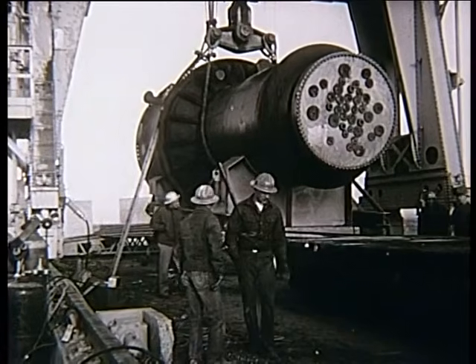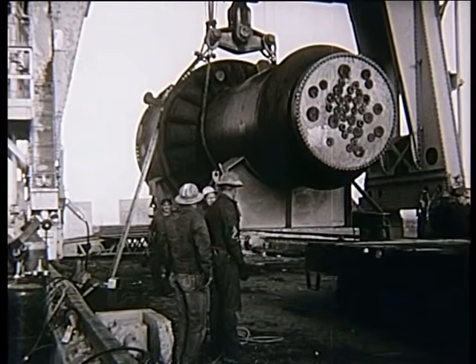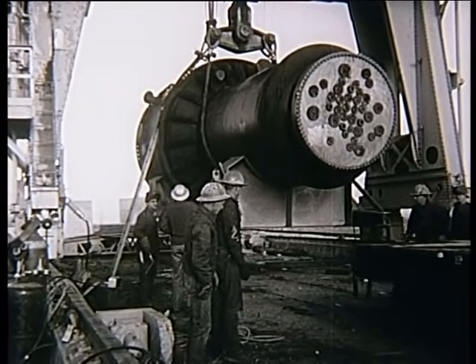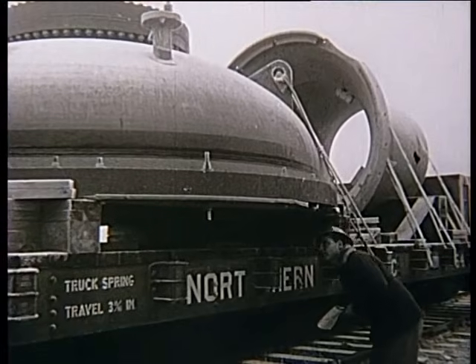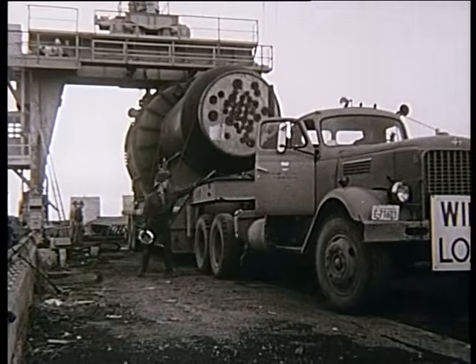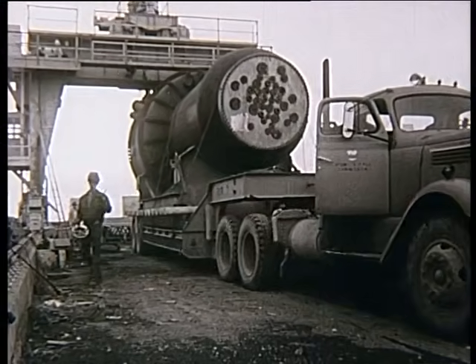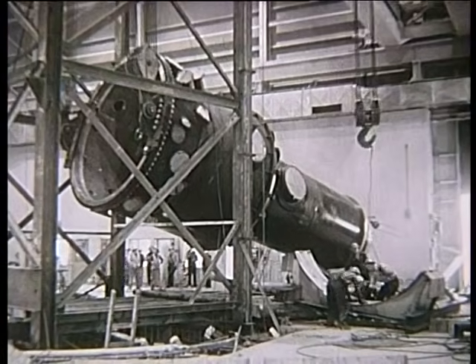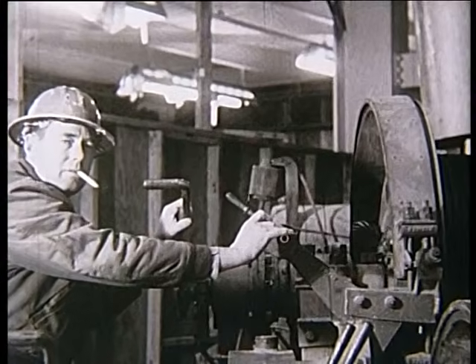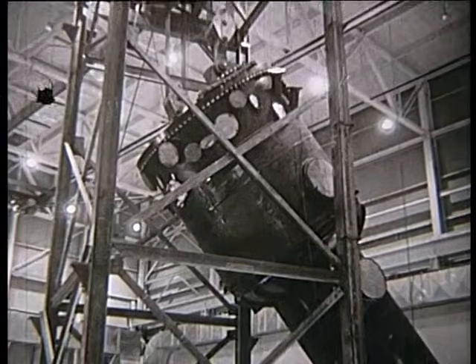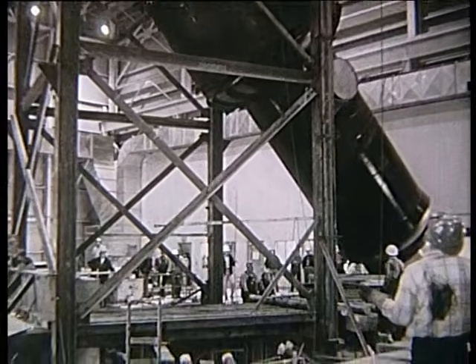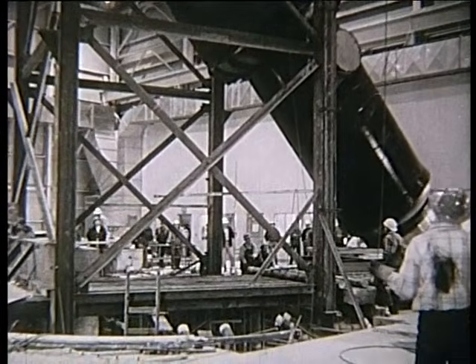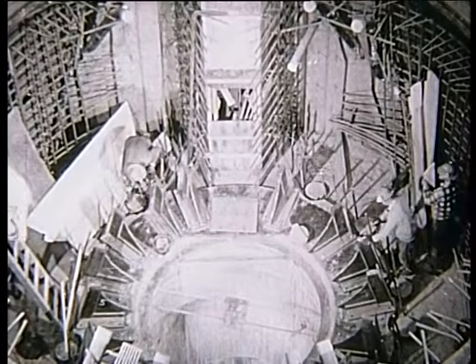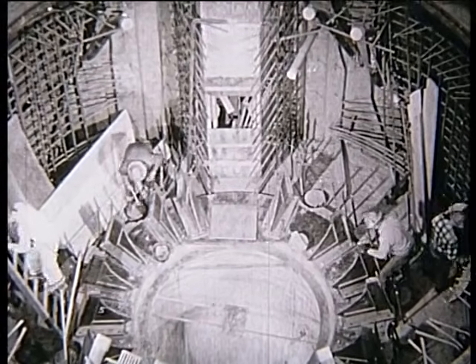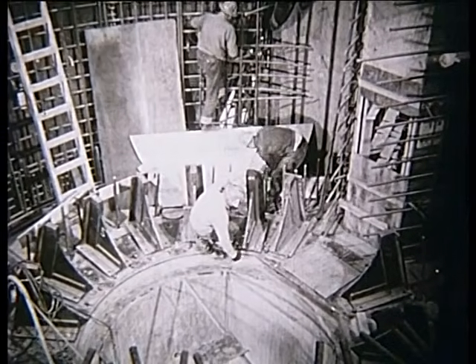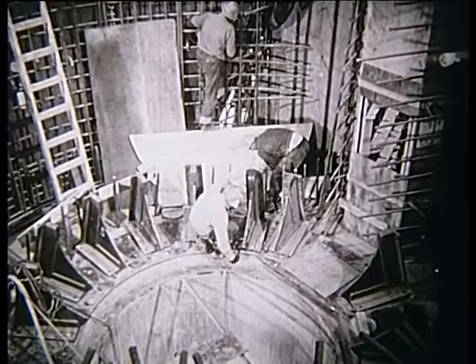The 150,000-pound pressure vessel was fabricated in Boston, Massachusetts, some 3,000 miles from Idaho, and was delivered on special railroad equipment. Shipping difficulties made it necessary to remove some of the exterior equipment, such as nozzles and flanges, which were replaced upon arrival. The vessel is made of carbon steel with interior cladding of stainless steel. It is about 35 feet long and 12 feet in diameter at the top, with a lower section diameter of 8 feet. The pressure vessel is supported on a bed plate at the transition level, from the larger to the smaller diameter. This support method provides for thermal expansion of the vessel diametrically without excessive stress or movement.